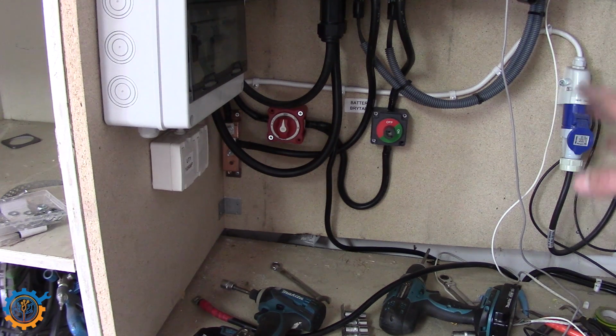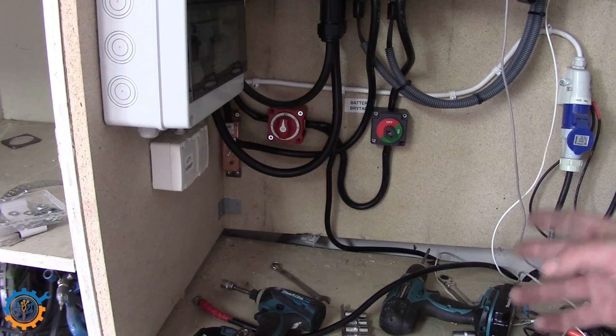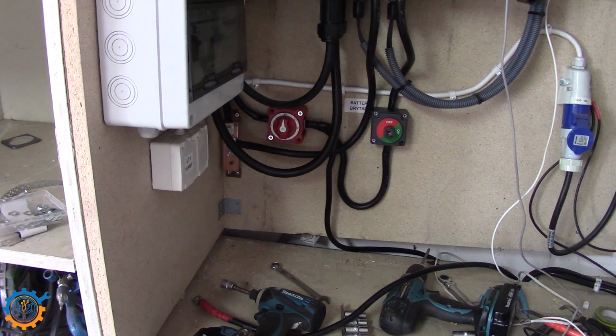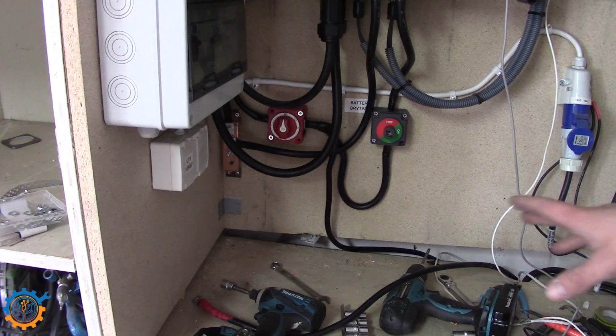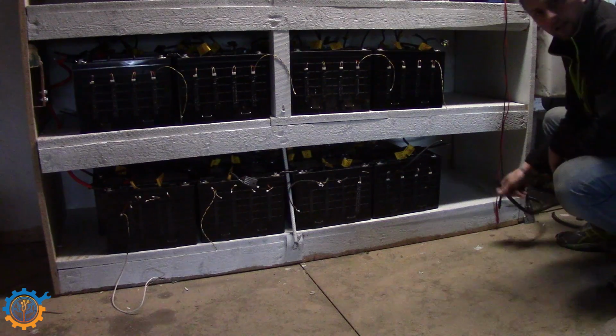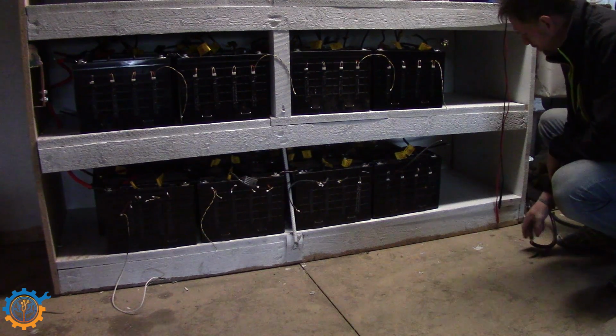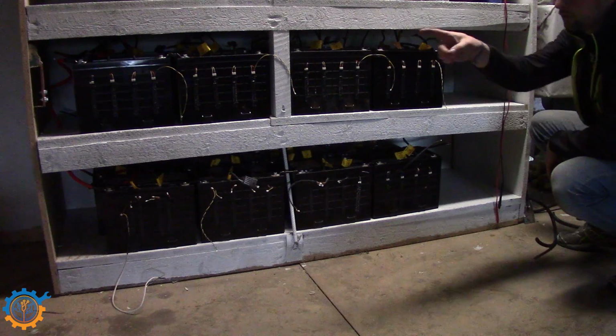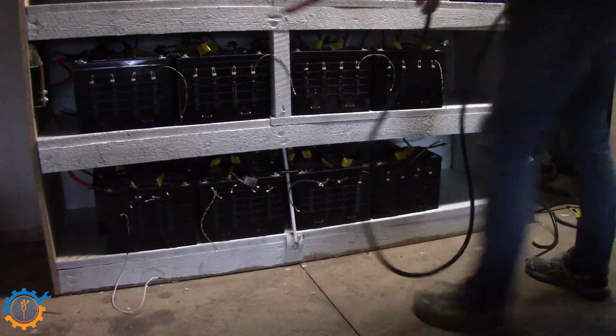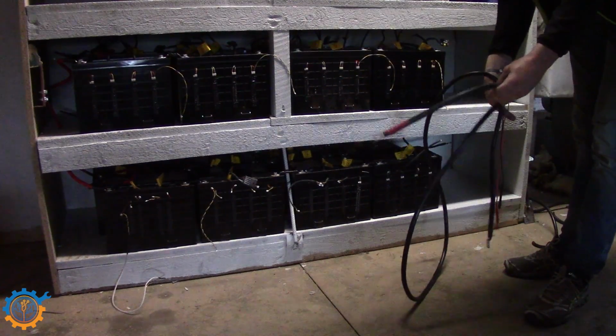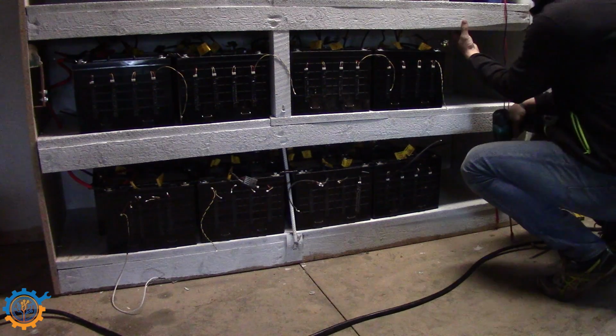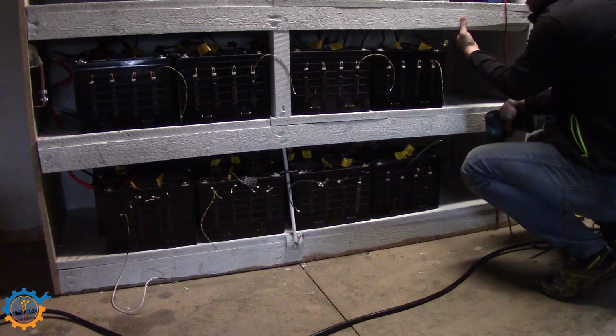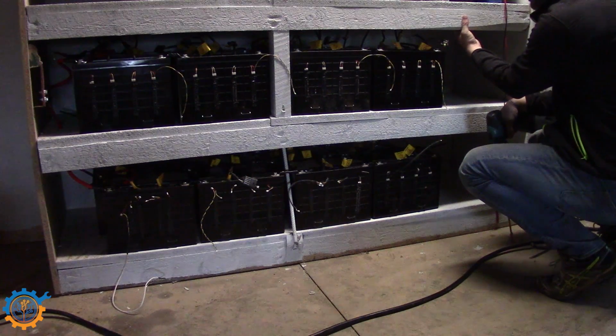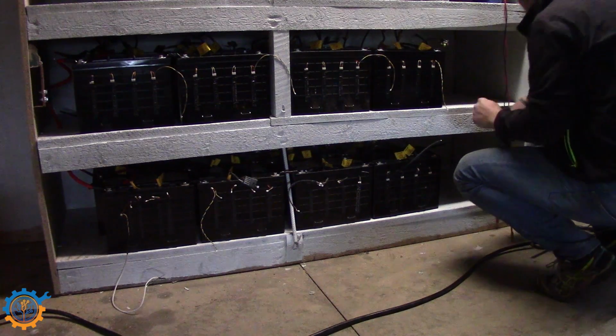Next part is actually to go back up and connect the batteries to the inverter as well, and then also hook in the BMS. We have the incoming cables at this end now, but this is the positive and we need to get it over there. I have the cable here, it's 50 square millimeter as well. This cable will be tied on the back side up here. That's a little bit tricky to get onto as well, but we'll do that later on.